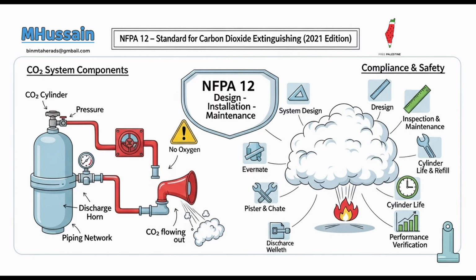For example, a No-4 nozzle indicates an equivalent 4/32-inch diameter orifice. Standardization for calculations. Exactly. This standardization ensures that during design and installation, engineers can precisely calculate flow rates and coverage, even with complex nozzle designs. If clogging is a risk, nozzles must be equipped with frangible discs or blowout caps that will rupture to clear any obstruction upon discharge. Blowout caps if they might get clogged.